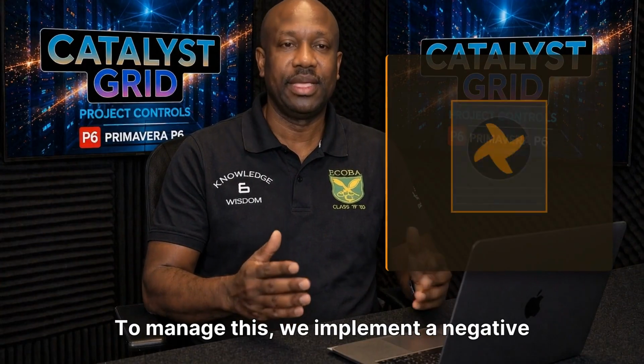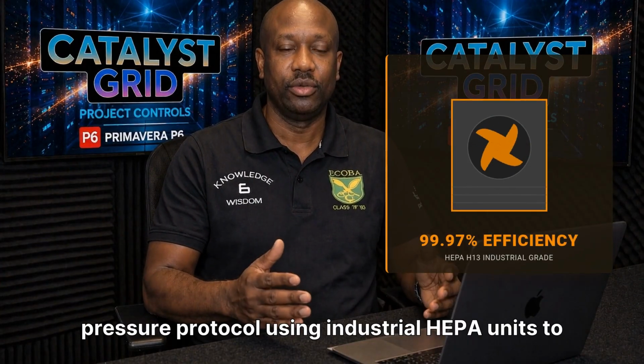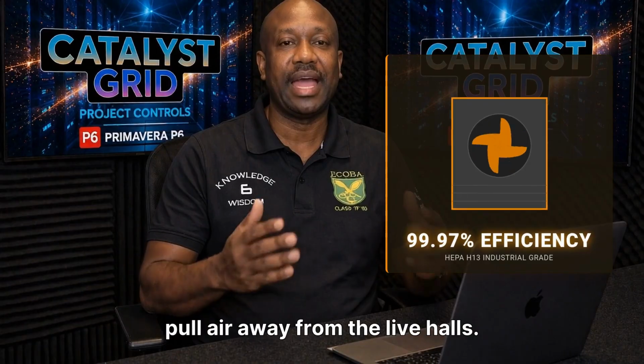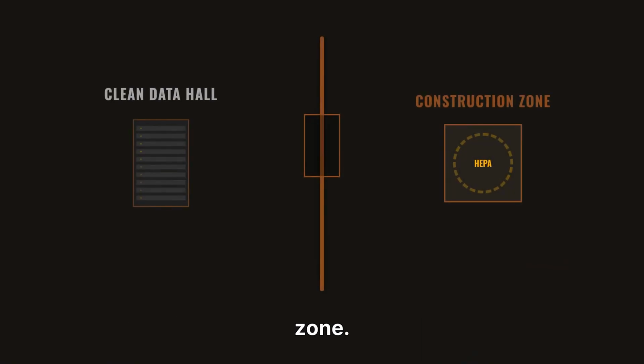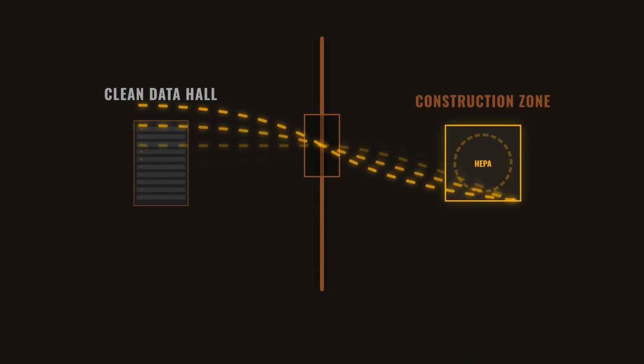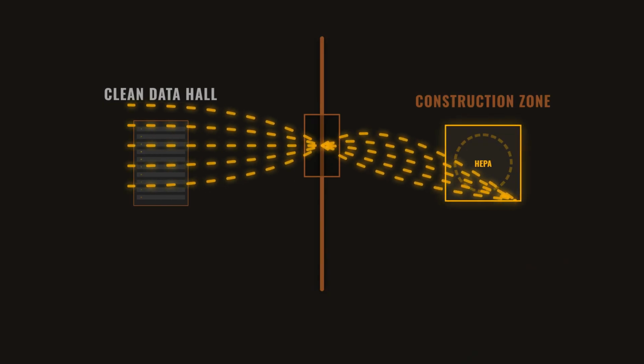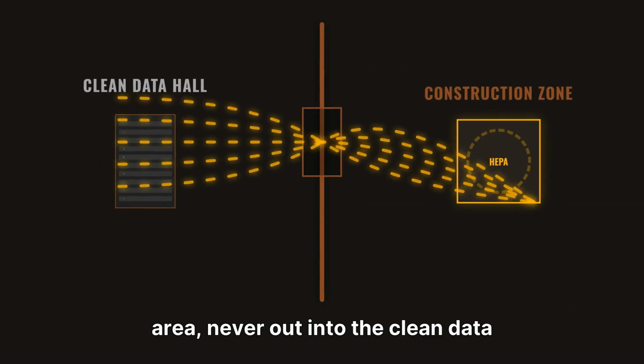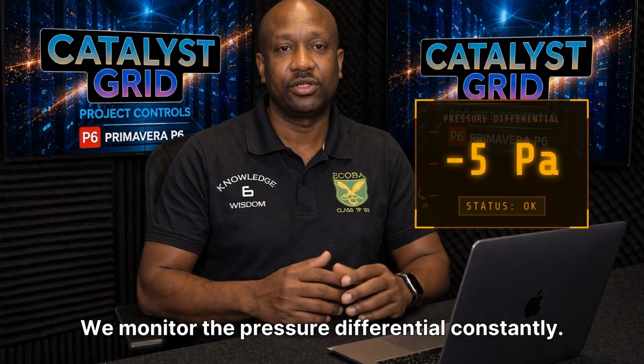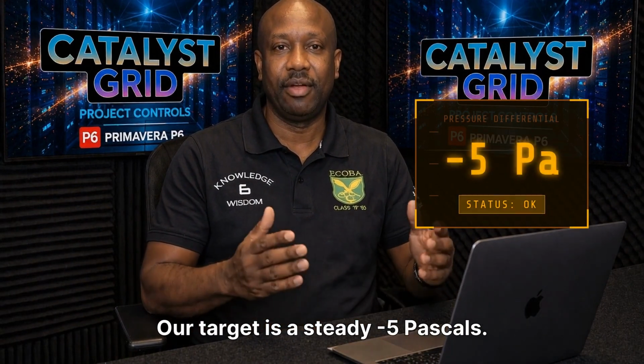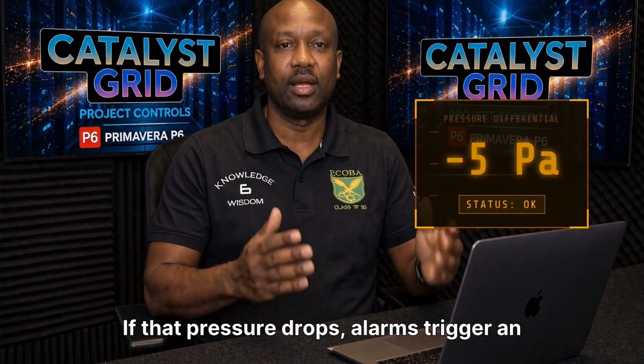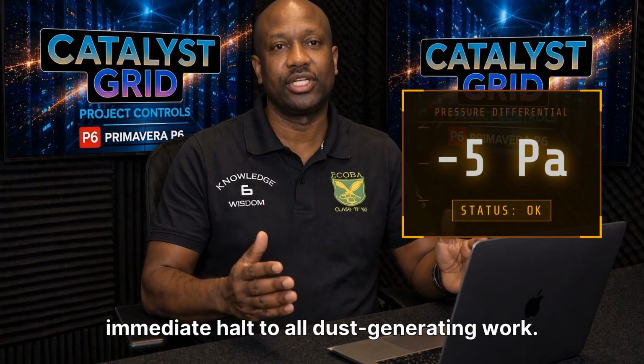To manage this, we implement a negative pressure protocol using industrial HEPA units to pull air away from the live halls. We maintain negative pressure in the construction zone. This ensures that any time a door is opened, air flows into the dirty area, never out into the clean data hall. We monitor the pressure differential constantly. Our target is a steady negative 5 pascals. If that pressure drops, alarms trigger an immediate halt to all dust-generating work.